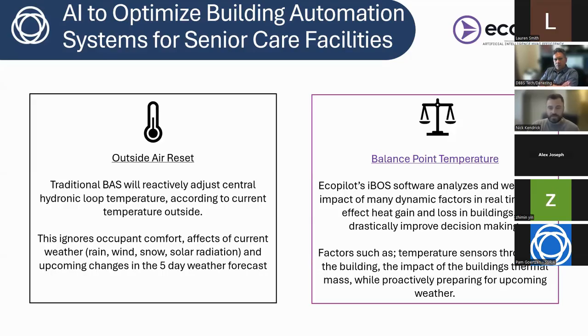So the difference between the classic way of keeping comfort in a building is called outside air reset. There's other ones too, like trim and respond and whatnot. Typically you'll see outside air reset, and what that looks like is, once the building's commissioned, they'll figure out at a given outside air temperature how much heat they want to put in that central heating loop to keep people comfortable in the building. As you can imagine, as the temperature changes throughout the day, it's going to bring that up and down. That's a reactive measure. What we want to do is be proactive, planning for the future, not just for the needs of the building right now, but also what's coming down the line.